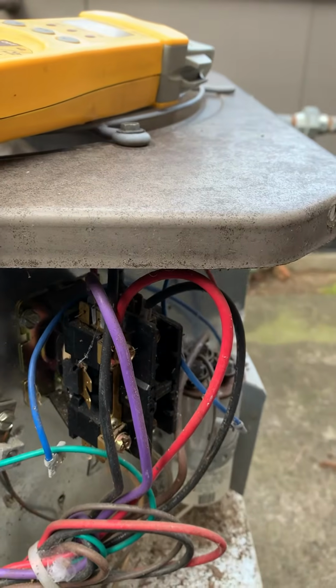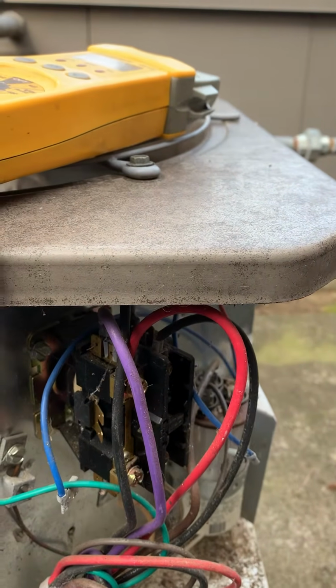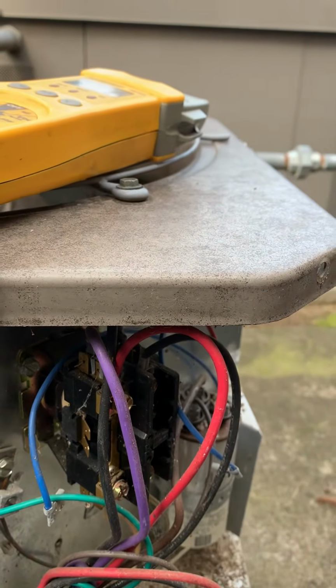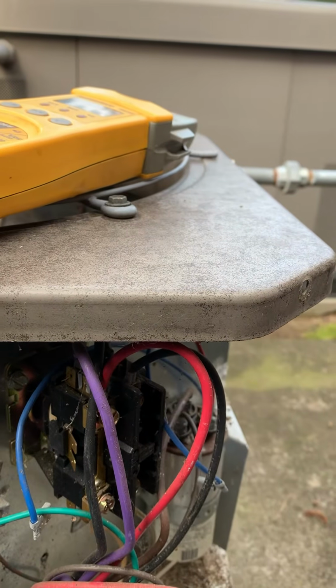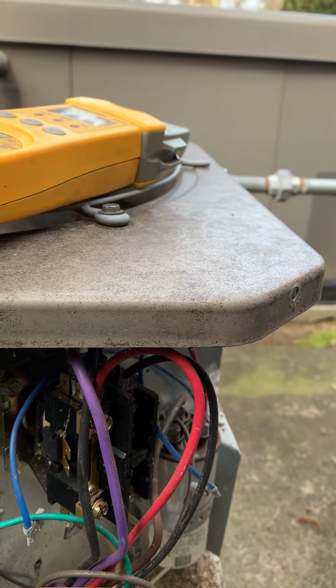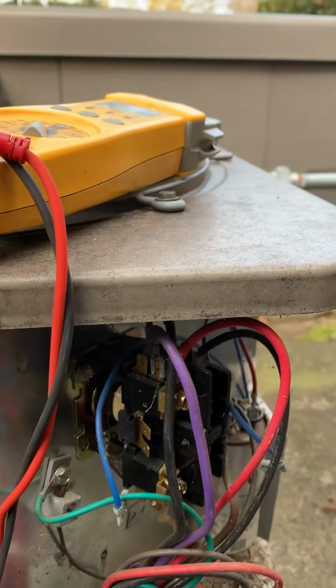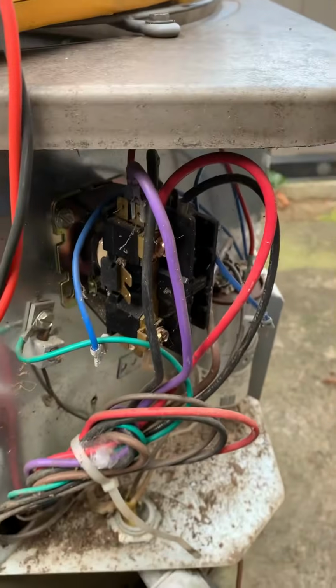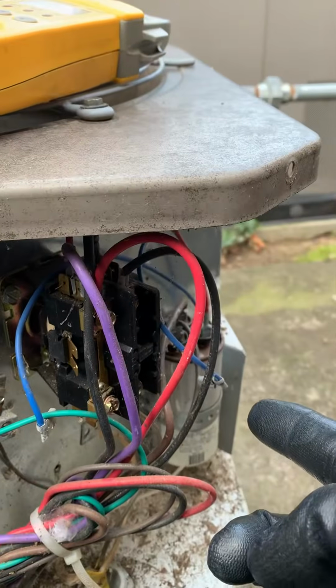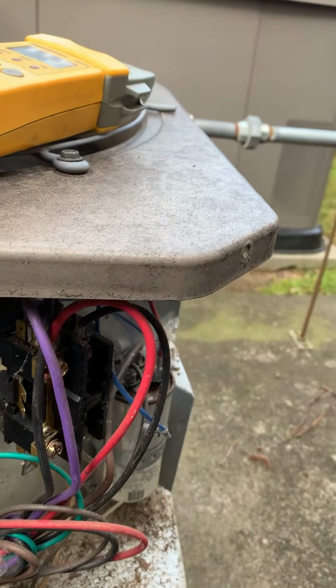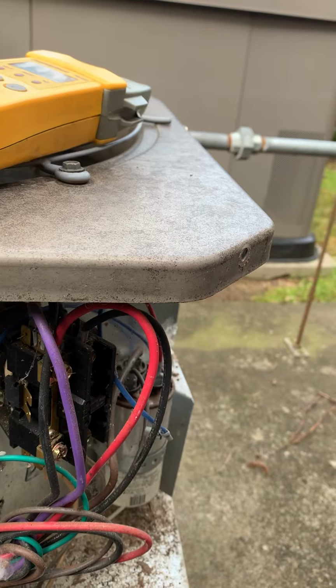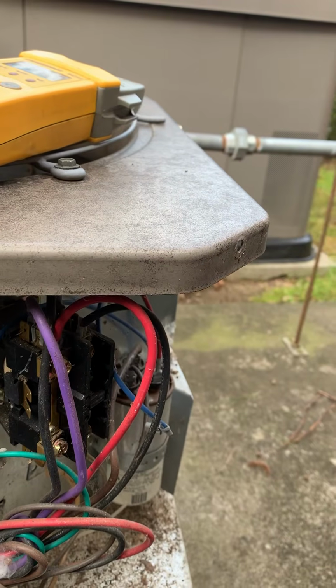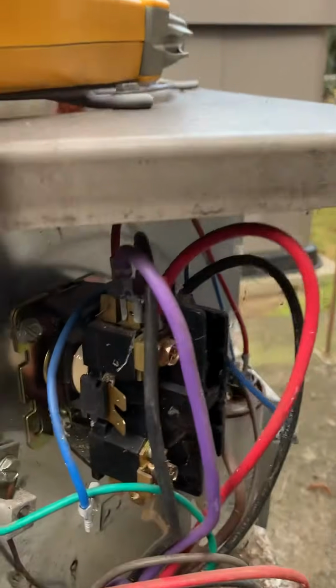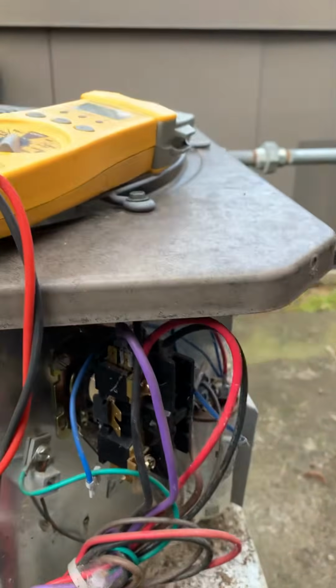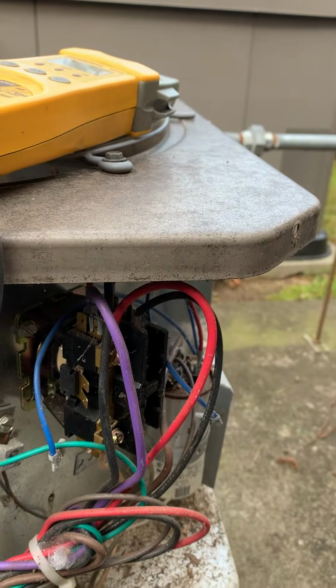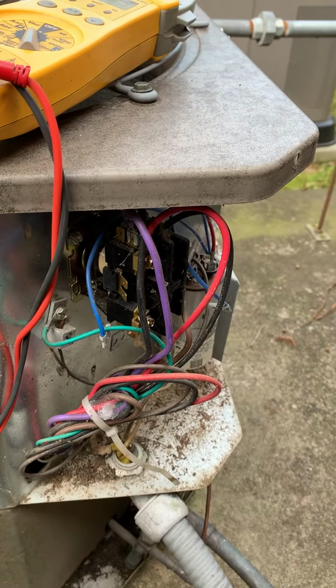What I'm going to do though is change out the contactor, because the low voltage on the transformer is popping, so it's nothing on the high voltage making the circuit breaker pop on the inside. It's all about the low voltage here. All right, so there's probably something up with the coil, because I got 24 volts from this wire here to that wire there, nothing abnormal. So I'm going to change out the contactor, and I'll continue the video and show you exactly what's going on. Normally there's probably something up with that coil. It's probably shorting out. All right, so let me change it up, and then I'll continue the video.